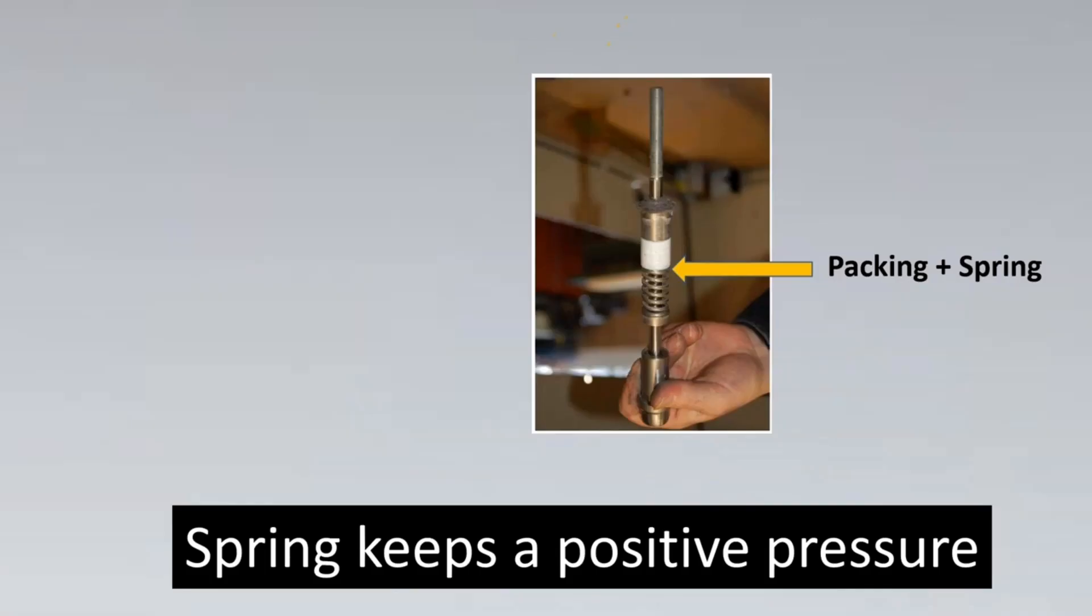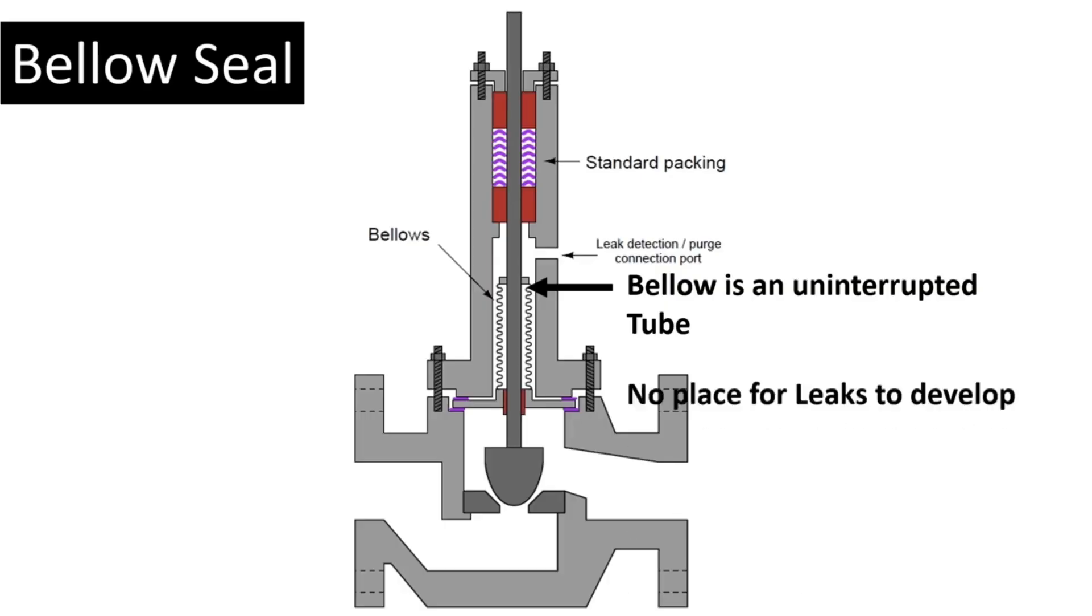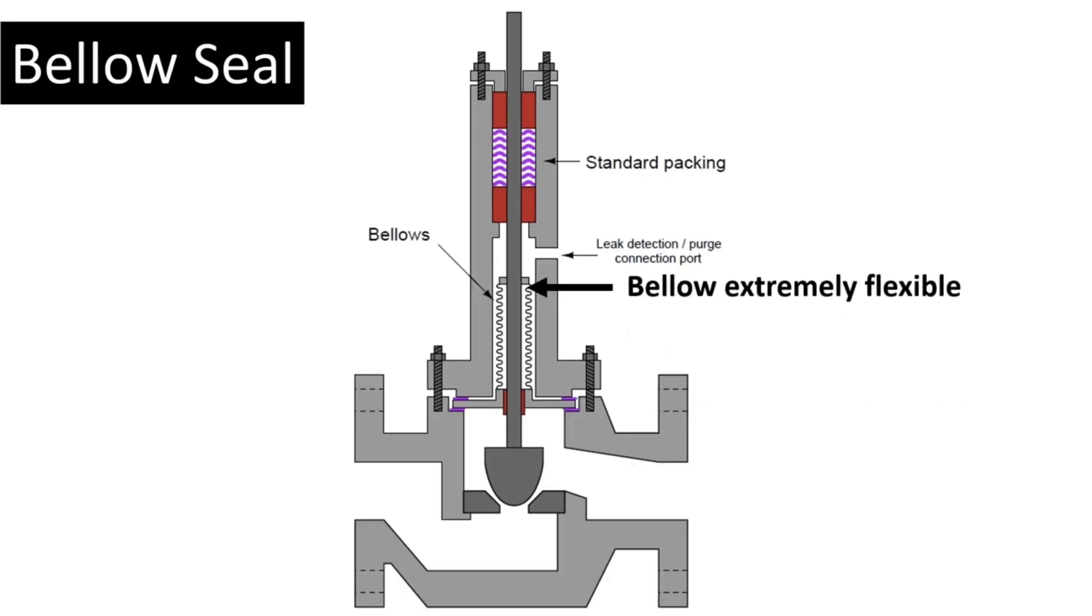Do we have another amazing way? Yes, we do. The next amazing way is something called bellow seal. This is a level up even than live loading. Here's your standard packing which is available. Here are your bellows and here's something called the leak detection port. Let's first focus on the bellow. Bellow is an uninterrupted tube, and if you see, it has no place for leaks to be developed.